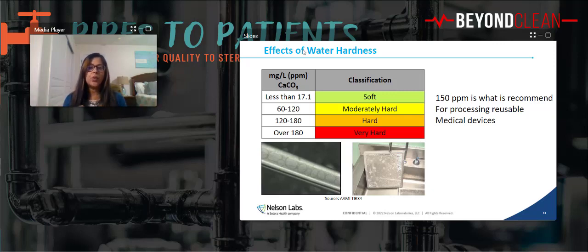And the main point is the spray arms should be free and dislodged of any of those calcium buildups, which we often see. And we see it in our lab, where we control the water, right? So I can just imagine what's happening in the field. You want to make sure that you have a descaling cycle that descales all of that. We do that at least once a week to make sure that we are removing any buildup that's in there.